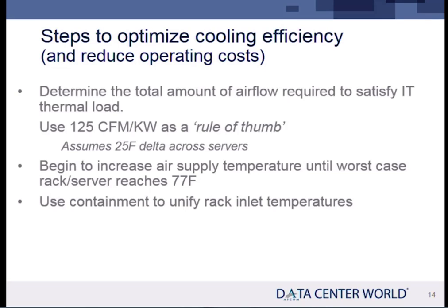The other thing I want to point out is there is a point of diminishing return on rack inlet. The ASHRAE spec for recommended rack inlet temp is 80.6F, okay? But most of us know that when you get to 77F, the fans start ramping up on the IT equipment. So this is something we've gotten to know over time. Yes, it's important to increase the supply temp until the fans on the IT equipment start ramping up, and it does improve your PUE, yes.